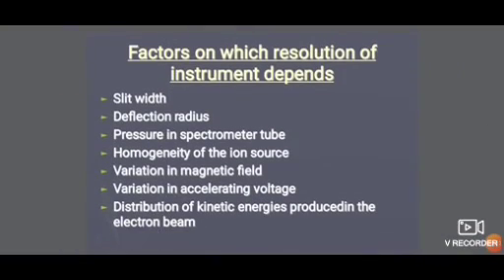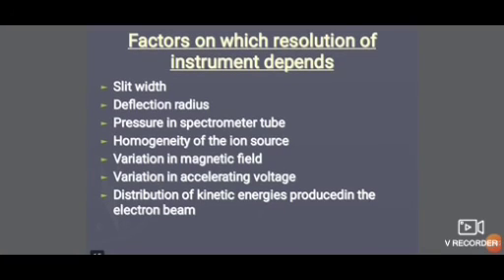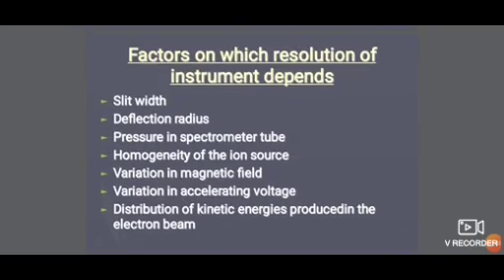The factors on which the resolution of the instrument depends are: first, slit width; second, deflection radius; third, pressure in the spectrometer tube; fourth, homogeneity of the ion source; fifth, variation in the magnetic field; sixth, variation in accelerating voltage; and seventh, distribution of kinetic energy produced in the electron beam. These are the factors which affect the resolution of the instrument.